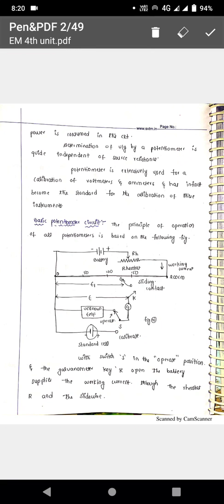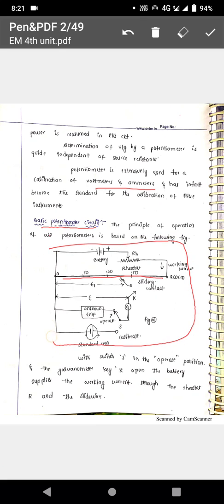To understand the potentiometer extensively used for voltmeter and ammeter calibration, we must understand the basic potentiometer circuit — the basic slide wire potentiometer. The principle of operation of all potentiometers is based on the slide wire potentiometer. One sliding contact and one slide wire of 200 cm length are used. It consists of one slide wire, one sliding contact, one switch and galvanometer, an unknown voltage source, and a standard cell.